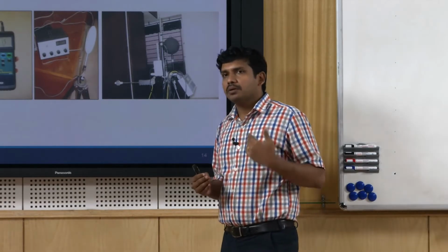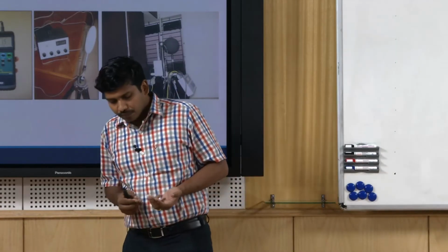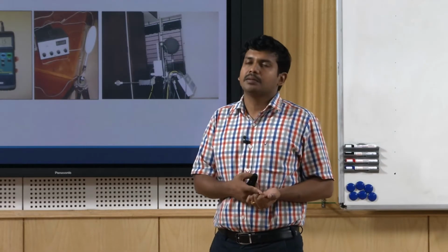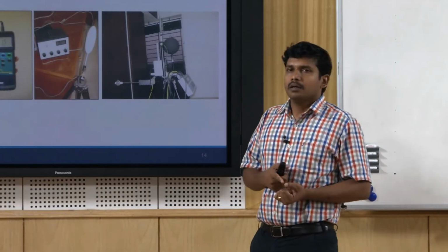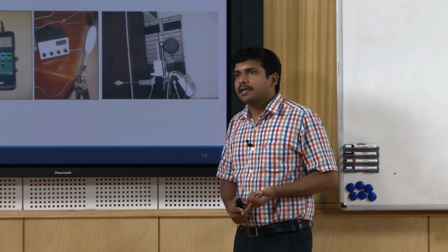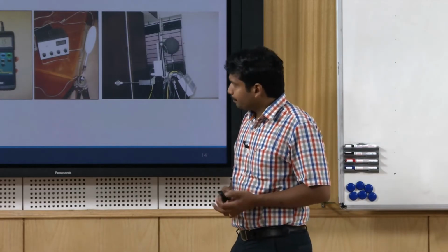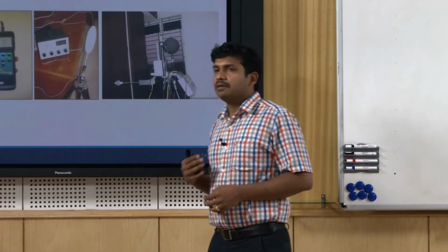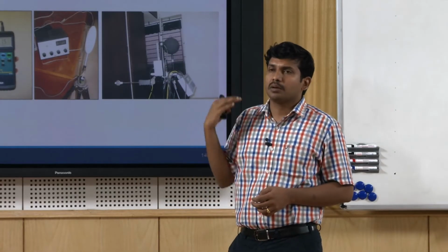As you go to level 2 surveys, you need to measure at least 4 environmental parameters: temperature, humidity, air velocity, as well as radiation, in terms of globe temperature. You would also have to note down their activity and metabolic activity and the clothing insulation.